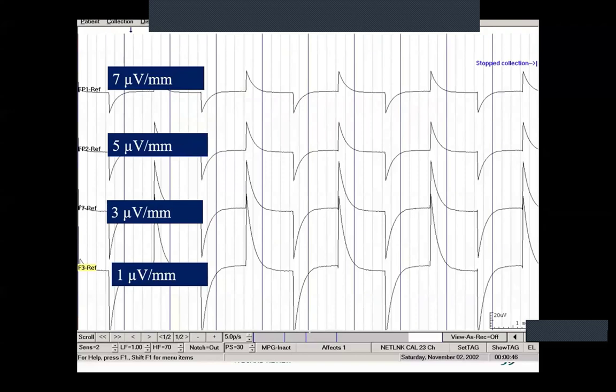Again, back to the square wave. And of course, I know most of you don't do square wave cal anymore, but I want to talk about the first 10 seconds of the EEG and respirations and EKG. Now, in this case, you'll notice if we started at 7 microvolts per millimeter and we turn it to 5, it gets bigger. We turn it to 3, it increases even more. We turn it to 1, it increases even more.